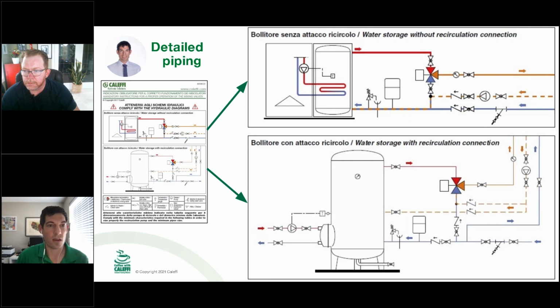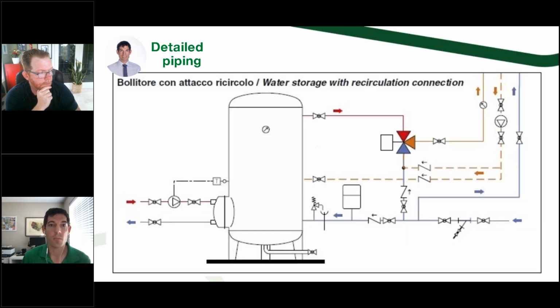So this is a sheet that we send in the box with all the Legio mix valves. The important thing, the difference, is you have two different options with the Legio mix, because it can close the hot water 100%. So in that case, you're recirculating whatever your maximum mix temperature was. It's going to dissipate some heat in that recirc line, either quickly or slowly, depending on the insulation. But you're not mixing blazing hot with warming temperature all night. It will just close that hot completely, and you don't have it creep.